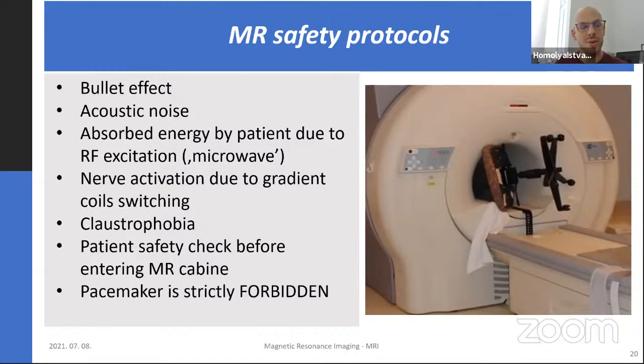So you always need to empty your pockets, remove your watch, your telephone, magnet card, coins, and everything. You can see in the image here how a simple chair can be sucked in by the magnet. It's very, very dangerous. So never forget, even if the scanner is not performing any measurements, the external magnetic field is always turned on. Yes, so patients with pacemakers are strictly forbidden to enter. We need to safety check them, obviously.